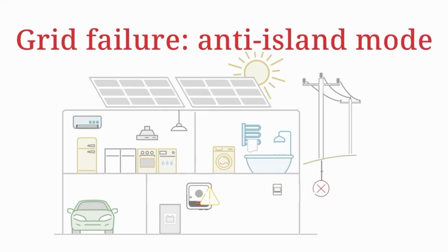If there's a grid failure, one of the responsibilities of the inverter is to enable anti-islanding mode. This means that the PV system is no longer able to generate electricity and potentially feed that back to the grid where somebody may be working to re-establish the grid connection. This is an important safety feature of grid-tied inverters.